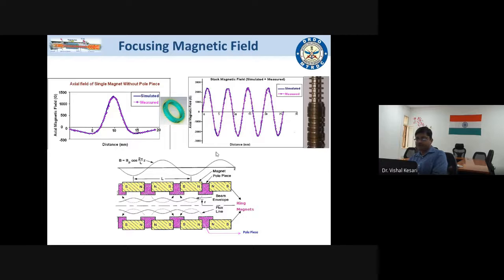Fine. Here you can see one of the tubes where the pole pieces are separated by spacers, and then these magnets have been put in different polarity, as we see S and N, and then N and S has to come. So this needs to be put. Because it is in this fashion, they will try to repel. That's why you can see over the structure some clips are put. That should be a non-magnetic material, so beryllium copper clips are being used to place the magnet in its position.